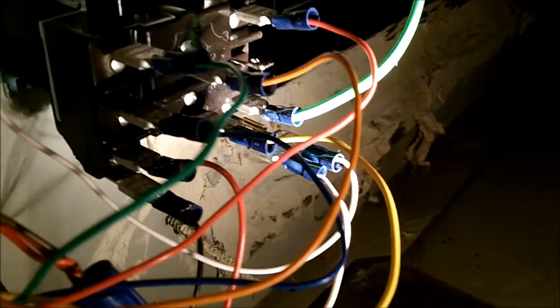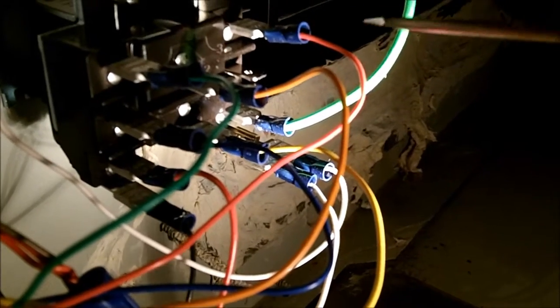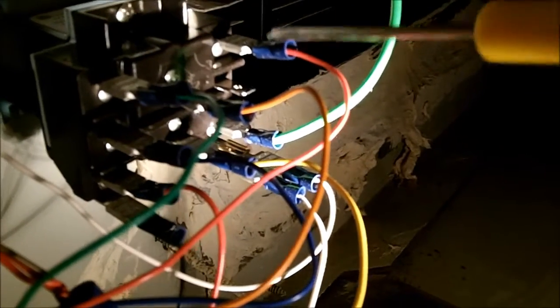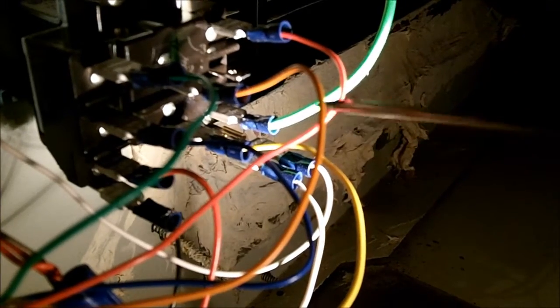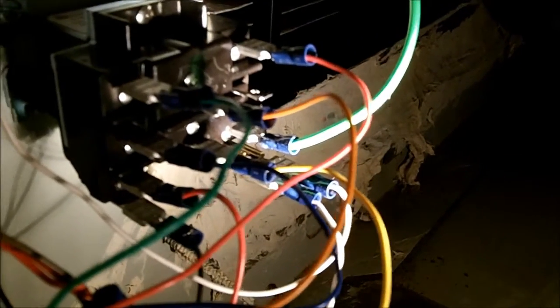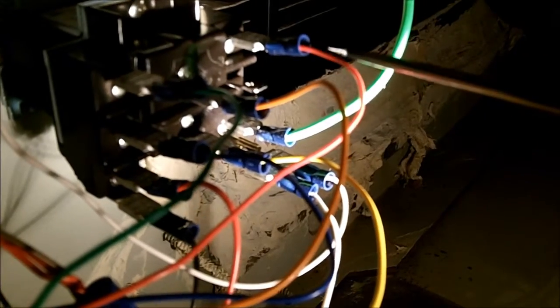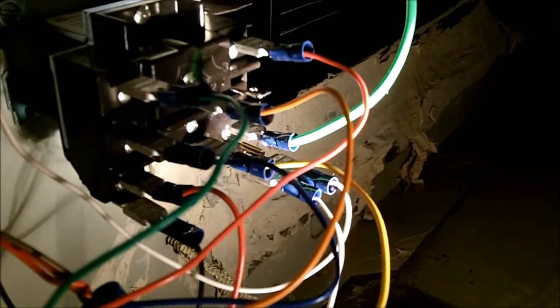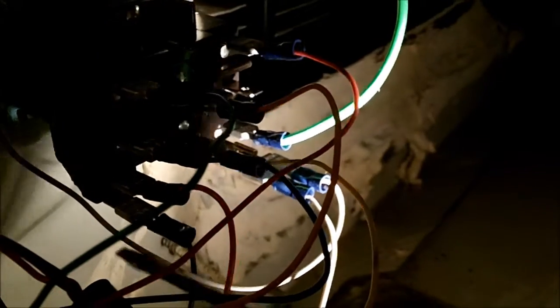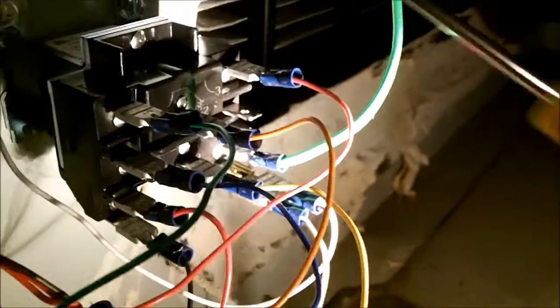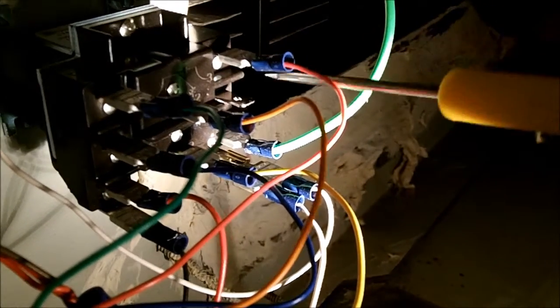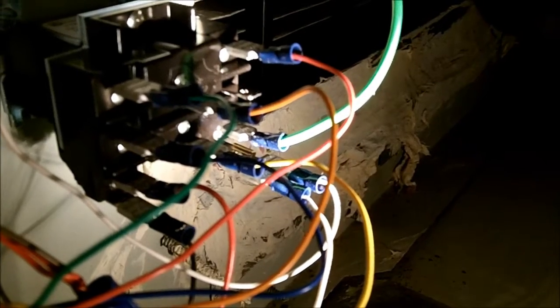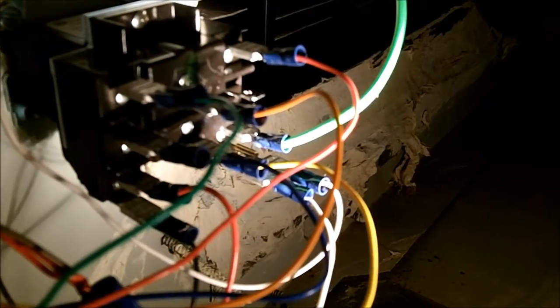At the top, this is a double pole double throw relay. So what I've done up here, wiring up the fan section of it, this red wire comes from the thermostat. It comes from the 24-volt hot. Since I've got this hooked up to the humidistat, when the humidistat calls, when it energizes the relay, it's going to send power from this terminal to this terminal. It's going to bring the fan on. That green wire heads up to the circuit board, so it's going to bring the fan on.